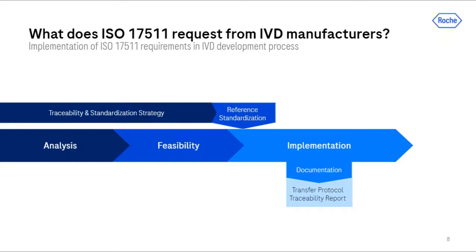In order to implement and fulfill all requirements of ISO 17511 during the development of an IVD device, the strategy for traceability and standardization has to be assessed in the process. The first validation lots produced after the feasibility phase have to undergo the so-called reference standardization, in which the traceability and value assignment is fixed. It is also checked whether the standardization process allows a feasible and consistent routine procedure, and the value assignment of all following lots will originate from this initial reference standardization. The defined calibration hierarchy is documented in a transfer protocol and a traceability report.